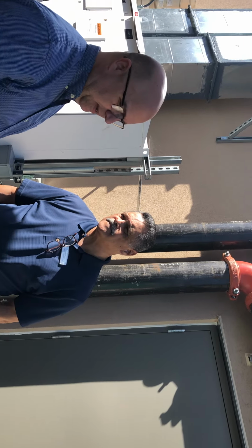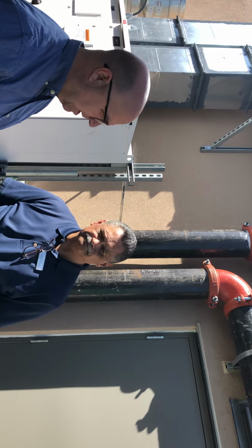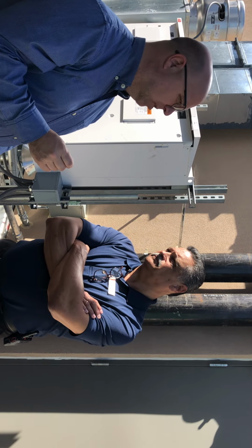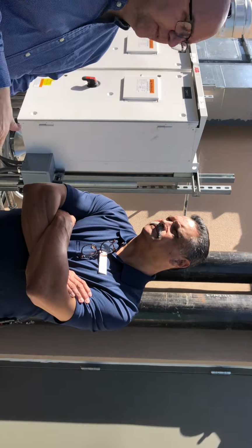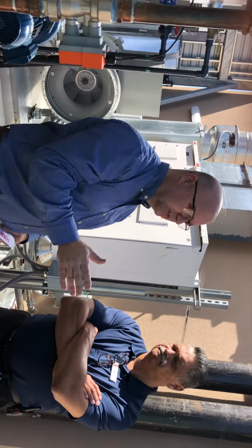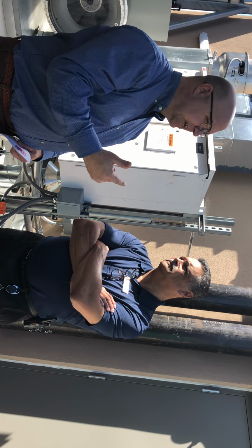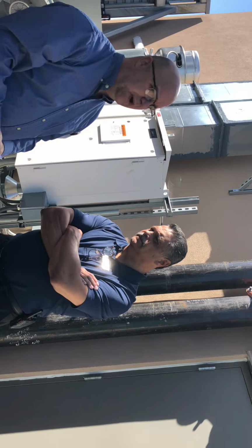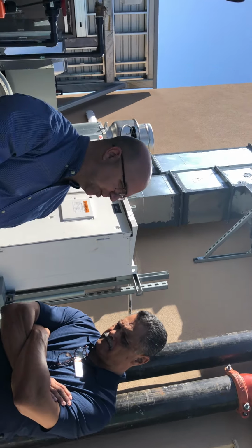Scattered across this roof and the upper roof are all sorts of exhaust fans, supply fans, and makeup air units. There are a handful of fans controlled by the fire alarm system. We don't control them, we simply monitor them. So we're building a table of all the fans showing what's actually running versus shut off. A fan being off isn't necessarily a bad thing. Some of the stairwell pressurization fans don't need to turn on unless there's a fire, and then it pressurizes the floor. So you'll have a table showing the on-off status of everything and the control status.